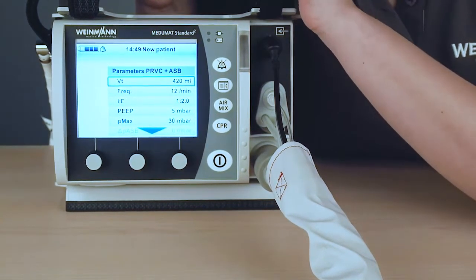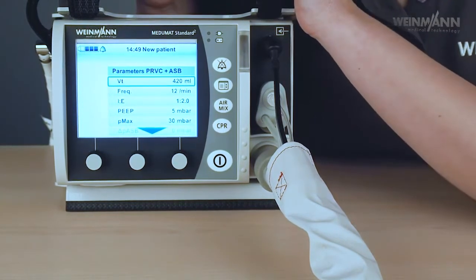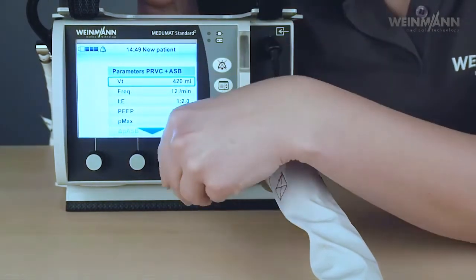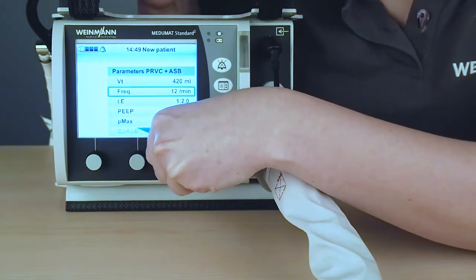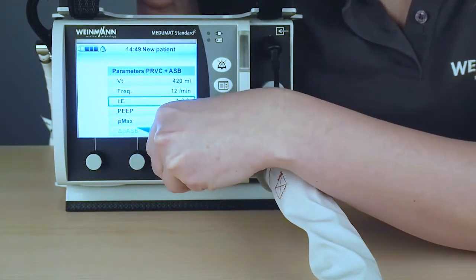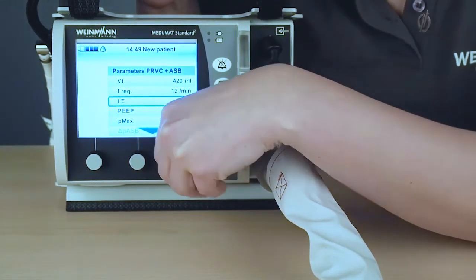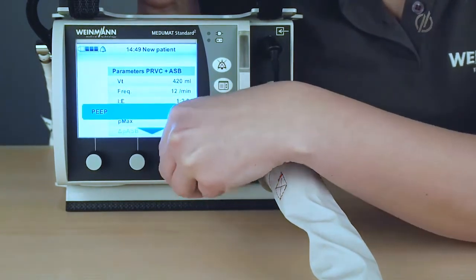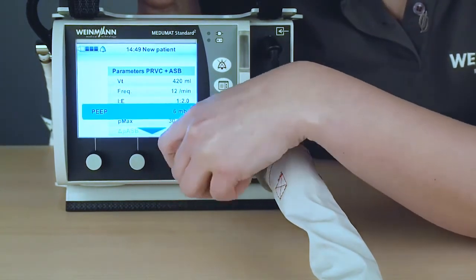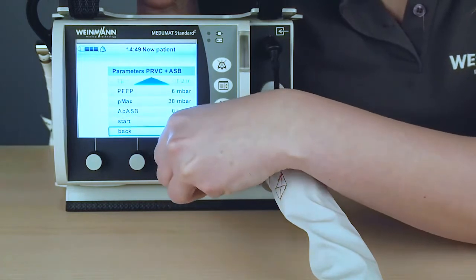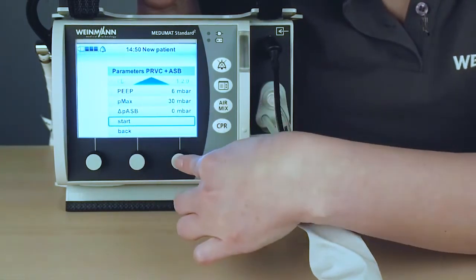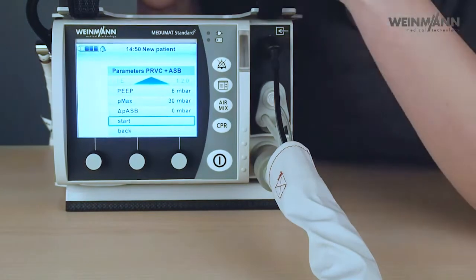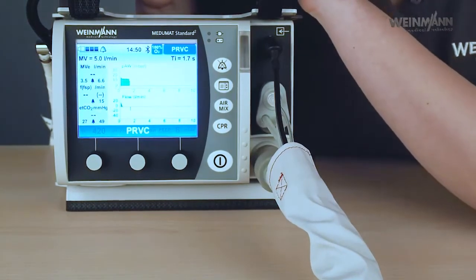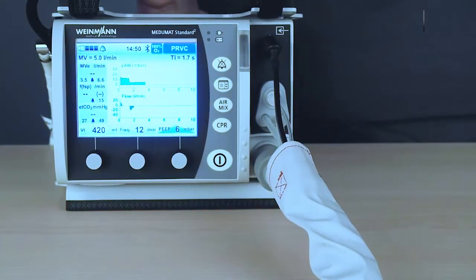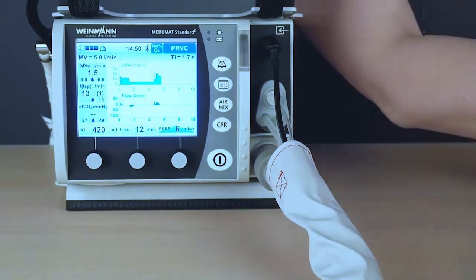420 in this case, this equals 6 milliliters per kilogram body weight. Also, the frequency is calculated by the height and the inspiratory to expiratory ratio. But I have also the possibility to change the settings here. Now I would like to start my ventilation by pressing the knob. And now the device starts with the PRVC ventilation.